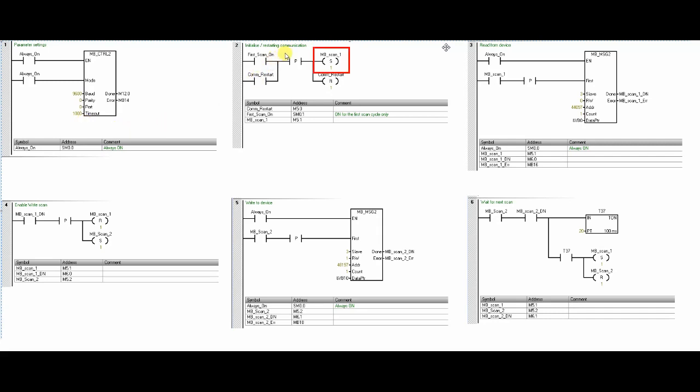Now in the second step, this MB_Scan_1 will be set with the first scan when the controller starts. I have also created a COM_Restart bit. This can be used to trigger the logic manually from the HMI or SCADA. So in case your communication fails, you can trigger this bit and restart the communication.